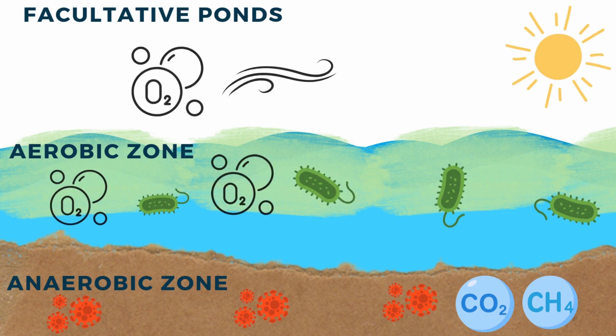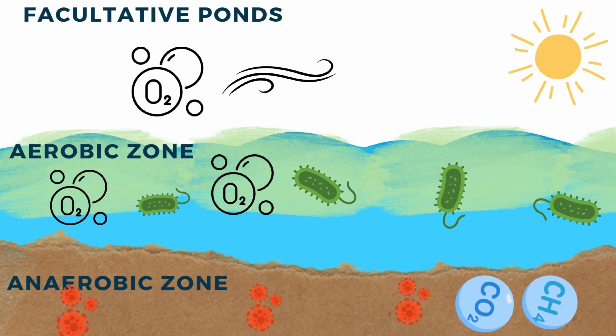There are three main types of oxidation ponds, each with different operational mechanisms depending on the depth and natural biological processes: facultative ponds, aerobic ponds, and anaerobic ponds. Facultative ponds are the most common type of oxidation ponds and operate through a combination of aerobic and anaerobic processes. It has a depth typically between 1 to 2 meters. It is suitable for treating domestic wastewater and industrial effluent.